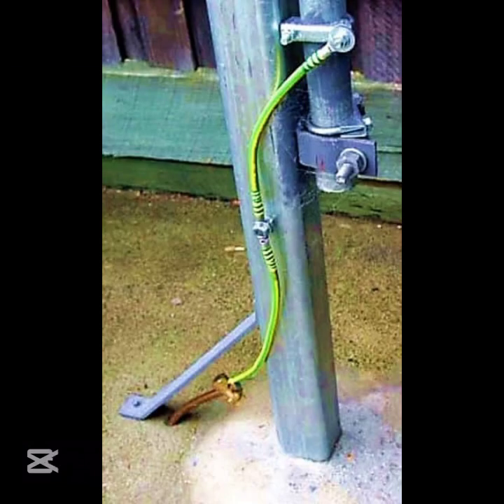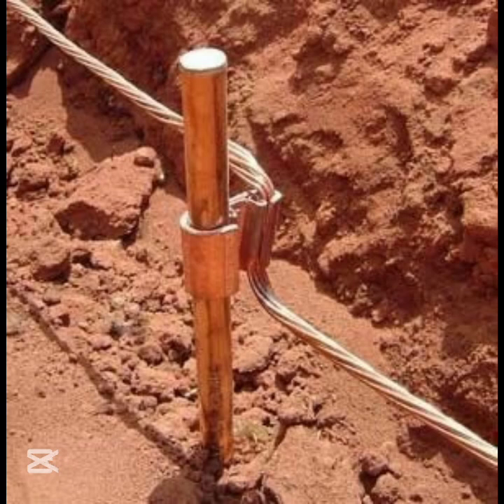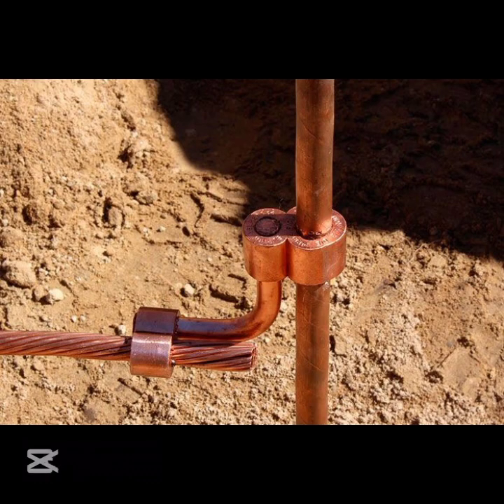Number 2. Grounding or earthing systems. Grounding systems provide a safe path for electrical currents to dissipate into the earth. This is crucial during lightning strikes, as it helps prevent excess voltage from building up in the system. A good grounding system ensures that the voltage surge is safely directed into the ground, protecting both people and equipment. Proper grounding involves using conductive materials like copper rods, or plates buried in the earth, and maintaining low resistance.